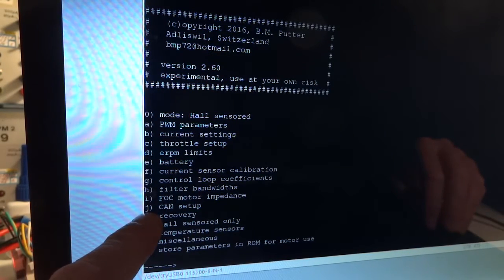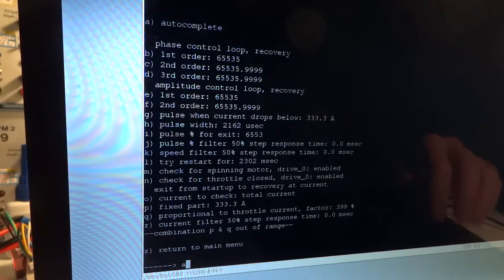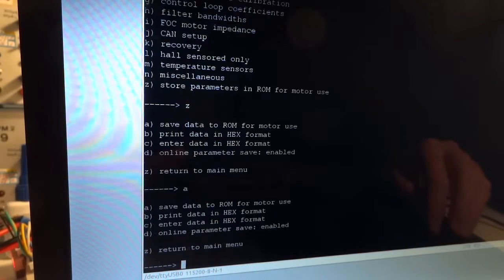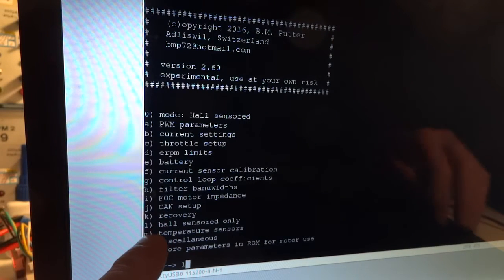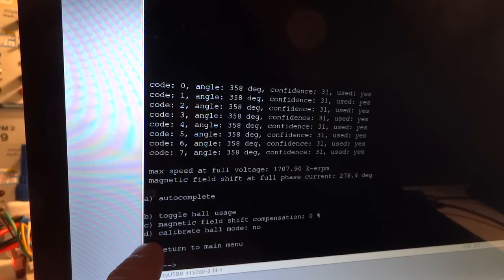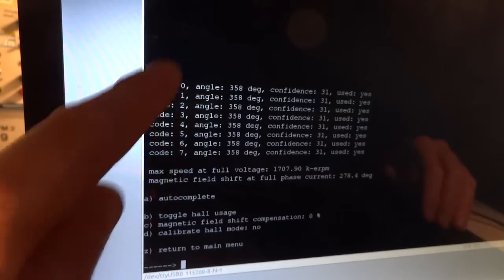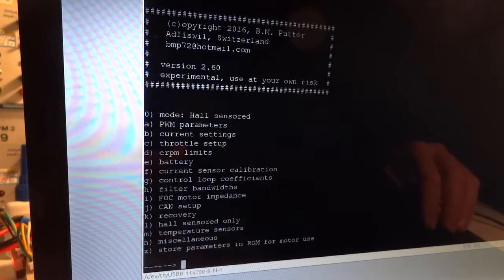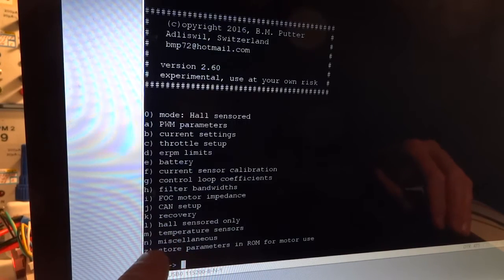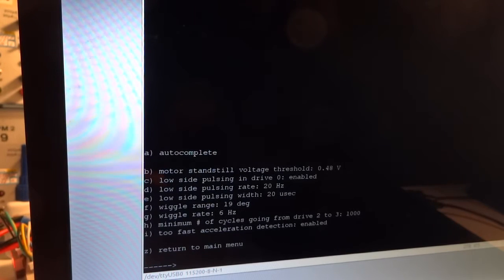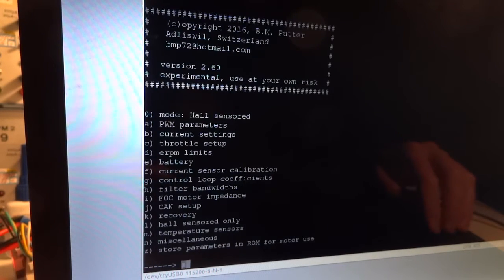Okay, CAN, if you don't use it, you don't need to look at it. Recovery, I typically autocomplete, that's it. Hall sensor, autocomplete. And since this is the first time I'm running it, I need to calibrate, because here you can see none of the Hall sensors are known yet. So I switch on calibration. Temperature sensors, don't have them, switch them off. Miscellaneous is typically just an autocomplete. And then store.